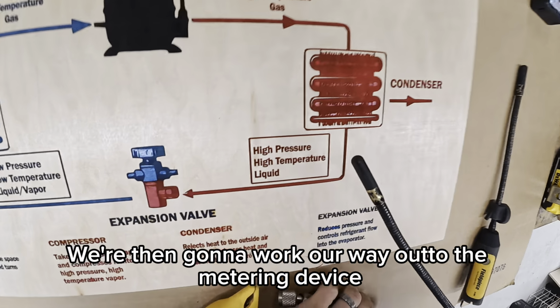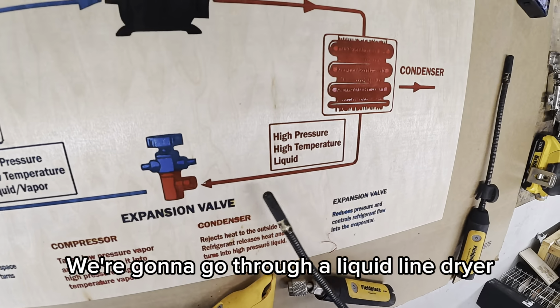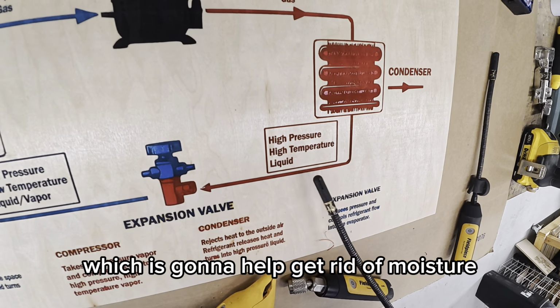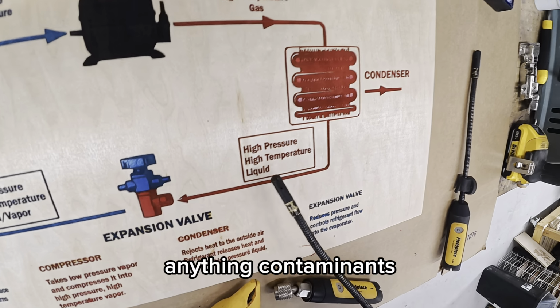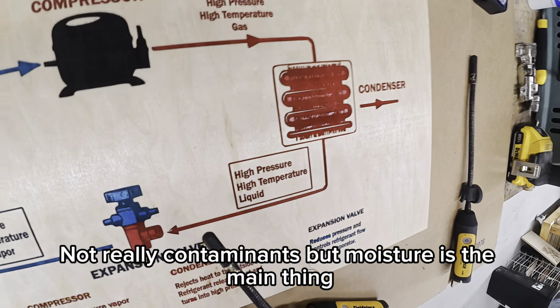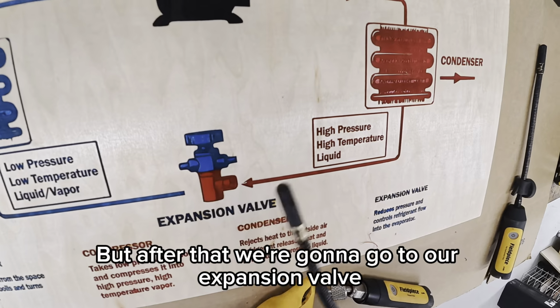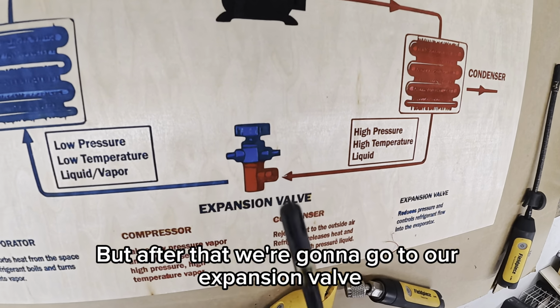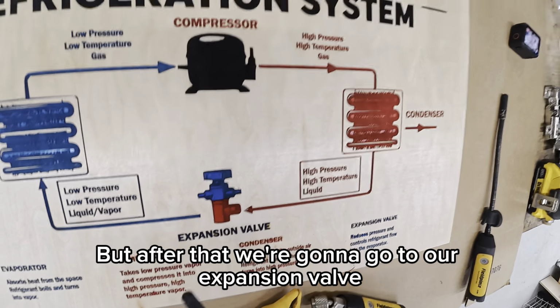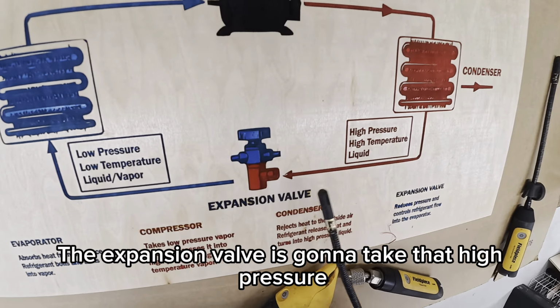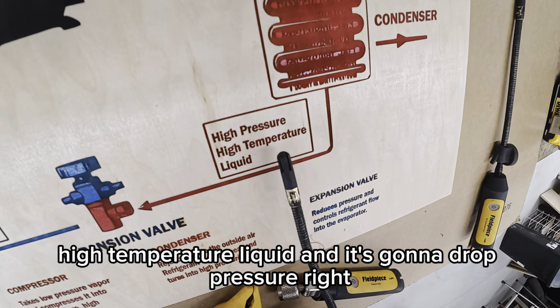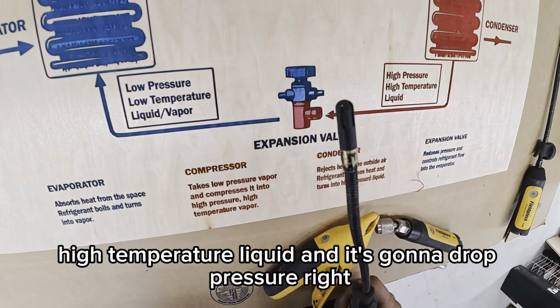So once we establish that liquid column, right, and we leave the condensing coil, we're then going to work our way out to the metering device. We're going to go through a liquid line dryer, which is going to help get rid of moisture. Not really contaminants, but moisture is the main thing it gets rid of. But after that, we're going to go to our expansion valve. The expansion valve is going to take that high pressure, high temperature liquid, and it's going to drop pressure, right?